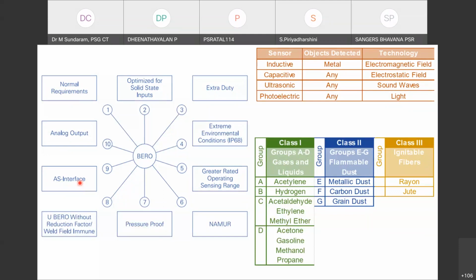According to the media - gas, liquids, flammable dust, ignitable fibers - it is classified into class and group: class 1, class 2, class 3. And what kind of chemical? Acetylene, hydrogen, ethylene - you see this in a lot of places, ethylene, methanol, gasoline, propane, even in biomedical industries and hospitals, and this metallic carbon grain dust, purely for industry. So most medical equipment falls into this class 1 category. We have to check this category - it's most important.